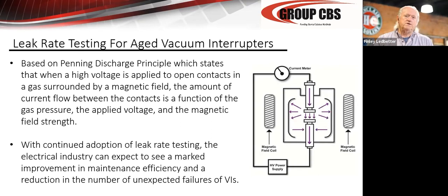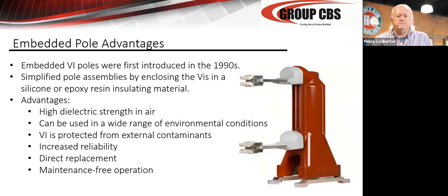No matter what test you use, DC, anything, basically before I tear that breaker down, I would put an AC high pot on it and run the go, no-go test, the very basic vacuum integrity test. That only tells you if the interrupter is good today. It doesn't tell you what it's going to do in the future. The Penning discharge test essentially gives you the vacuum pressure today, then you can get another spot in a couple of years and you can trend to failure. But the real acid test is the AC high pot vacuum integrity test. Be careful there. Once you reach near the failure point, you can get false negatives, false positives. So if it does show you a failure, believe it. And if it shows you a pass, don't believe it.